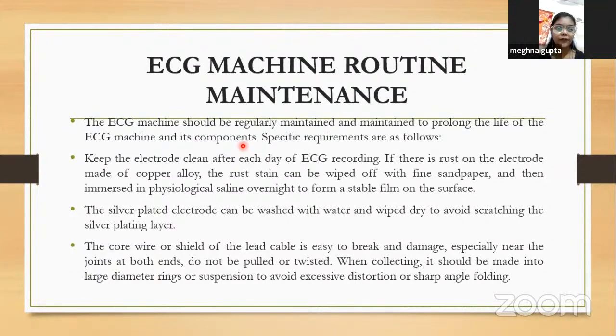The core wire or shield of the lead cable is easy to break and damage, especially near the joints at both ends. Do not pull or twist it. When collecting, it should be made into large diameter rings or suspension to avoid excessive distortion or sharp angle folding. जैसे देखा ना, काफी वायर्स हैं, अब उनको आप बहुत छोटे छोटे में कर दें या बहुत बुरी तरह पुल करें तो फिर वो डैमेज हो जाएगा. तो जो भी वो रीडिंग ले रहा है वो गलत होगा तो फिर डायग्नोसिस गलत होंगे. फिर नेचुरली जो मेडिसिन वो पेशेंट को मिल रहे हैं या सर्जरी जो भी हो रहा वो गलत होगा. तो handling that equipment is very essential: proper handling of the equipment, proper cleaning of the equipment, proper management of the equipment, that is very essential.